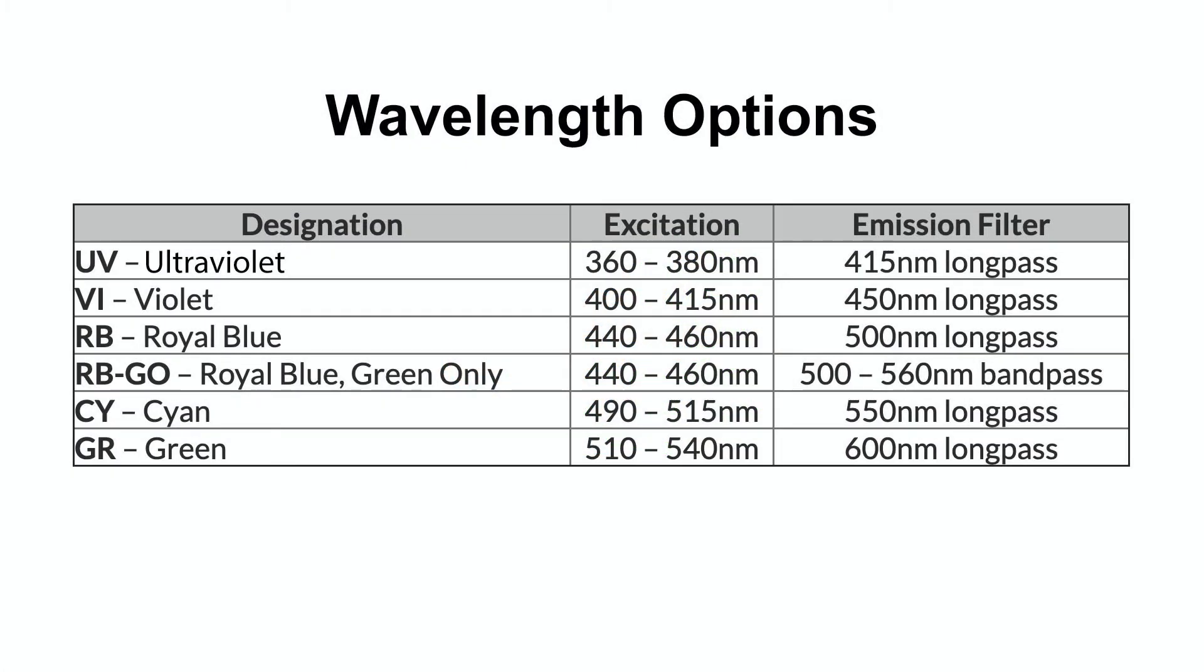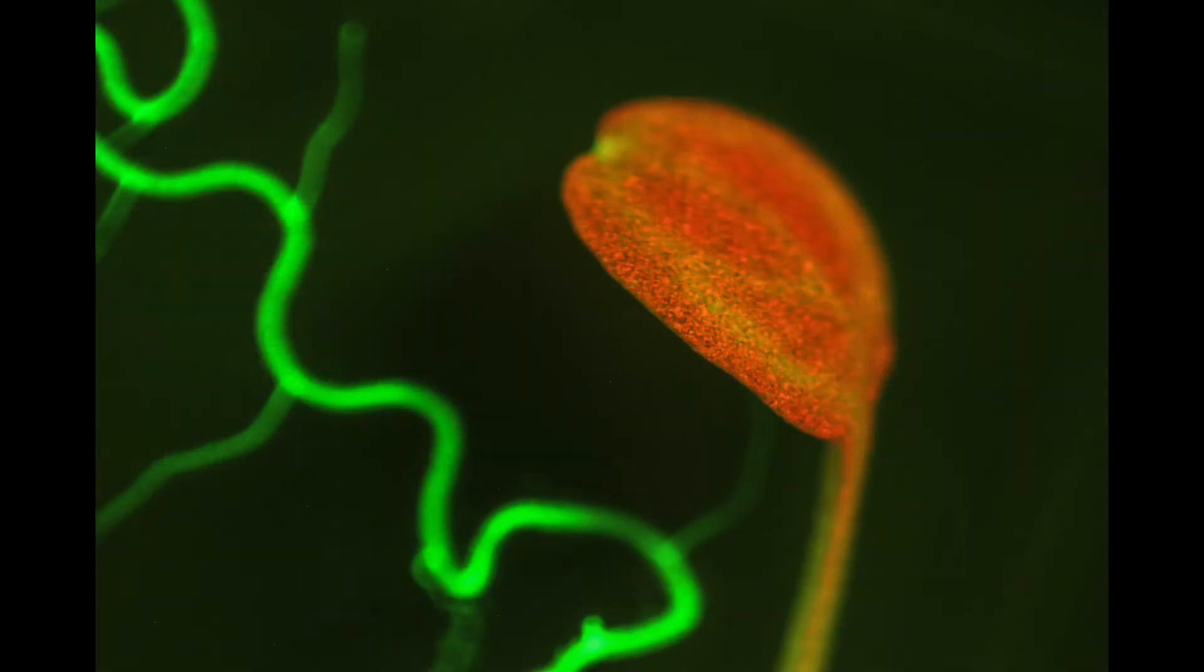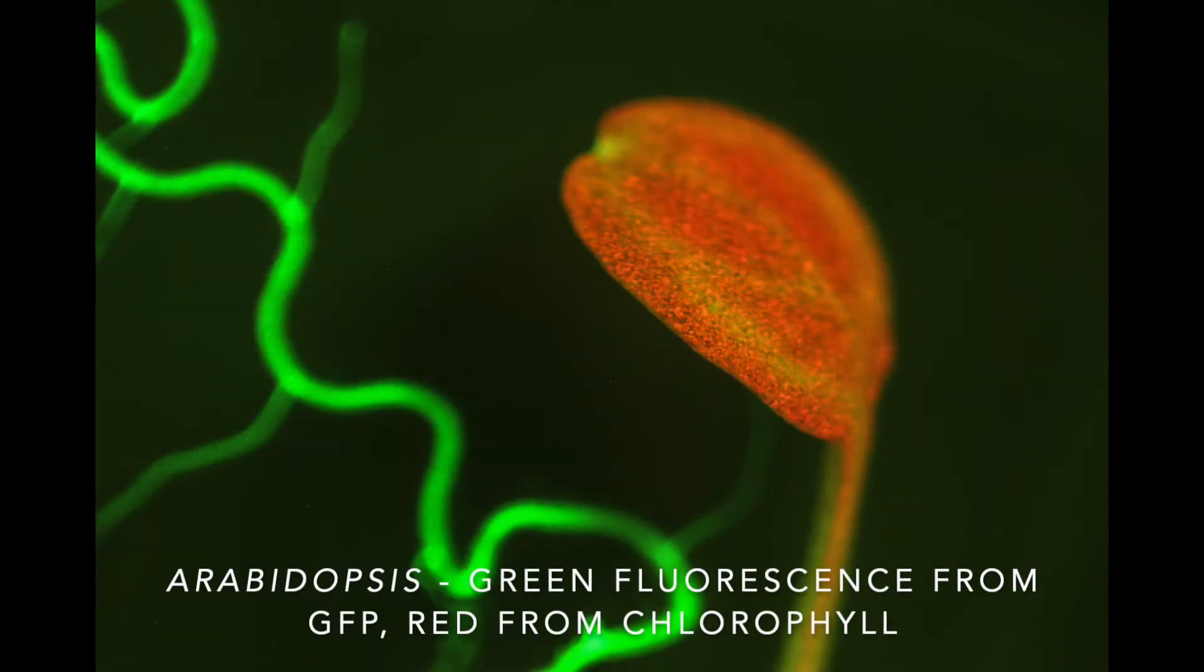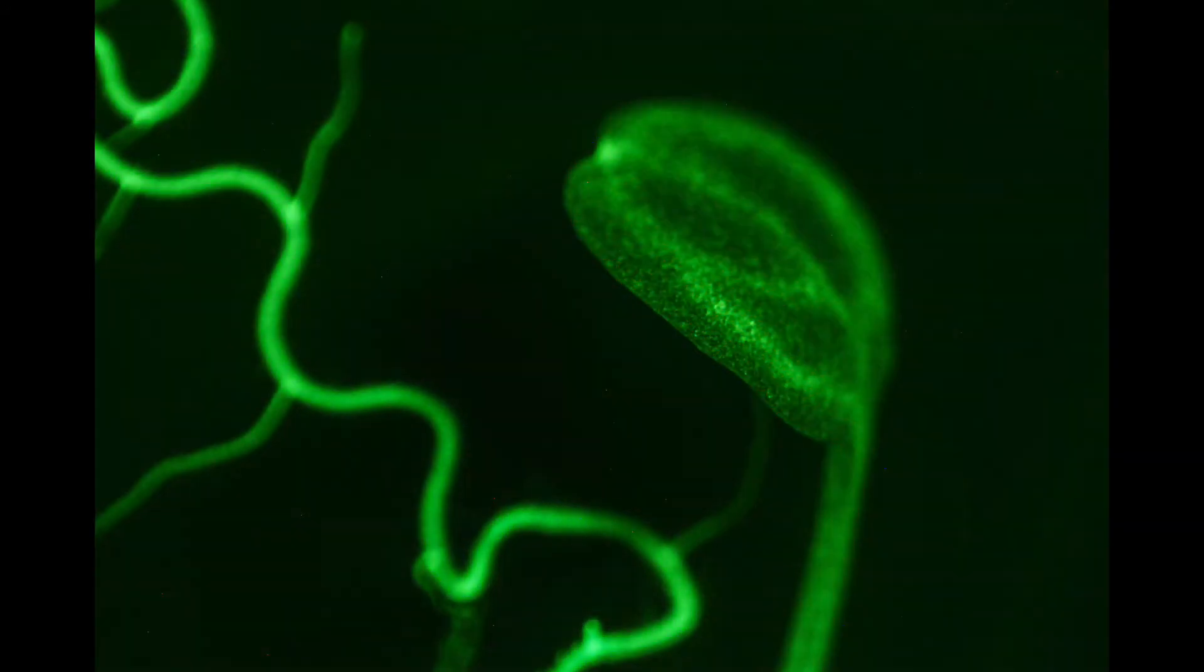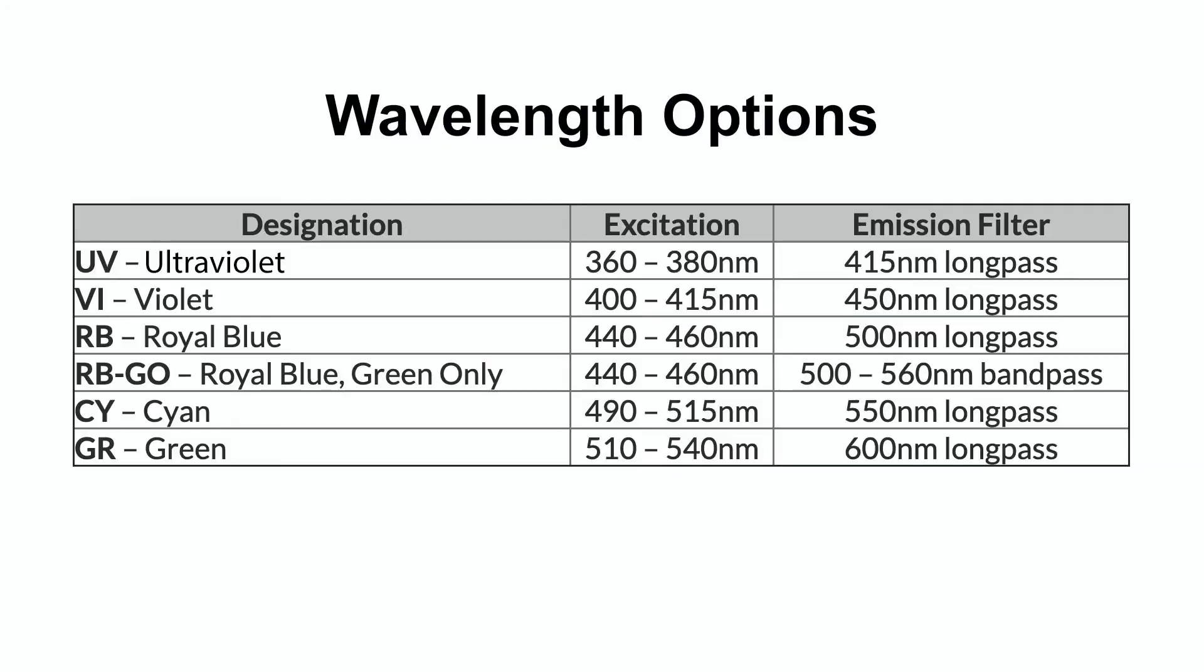Different subjects need different excitation wavelengths to make them fluoresce. This table summarizes the available excitation wavelengths and the corresponding filter glasses. Note that there are two different options for filter glasses with the royal blue excitation: long pass, which will transmit green, yellow, orange and red fluorescence, and band pass, which only transmits green fluorescence. The purpose and use of these two options is explained on the Nightsea website.